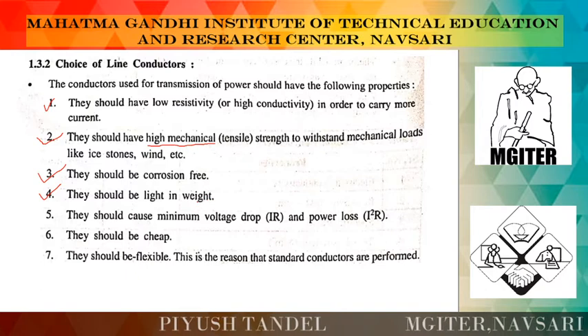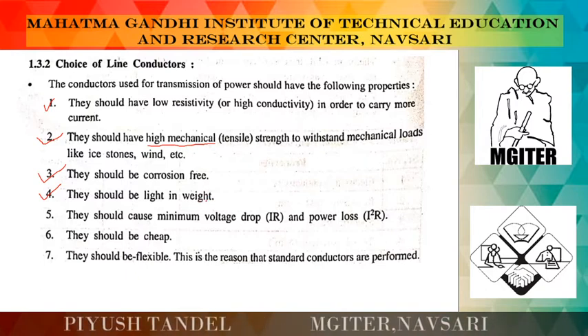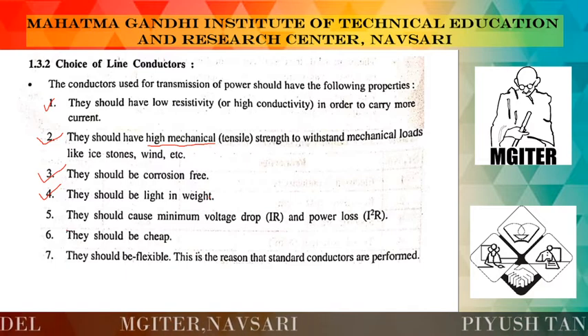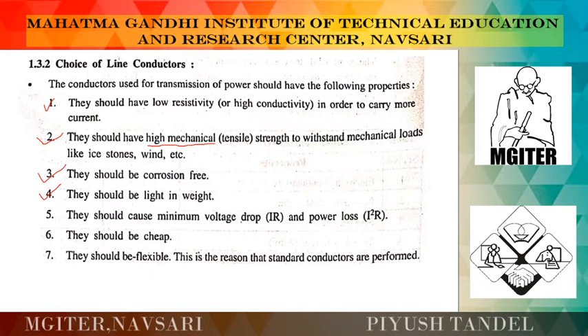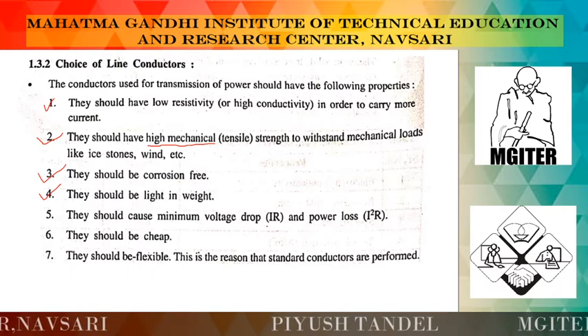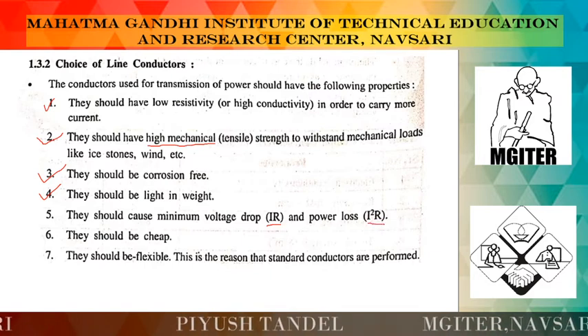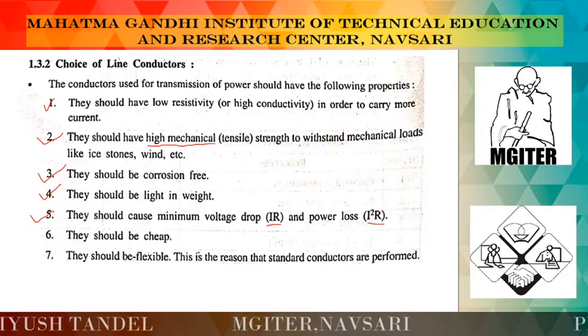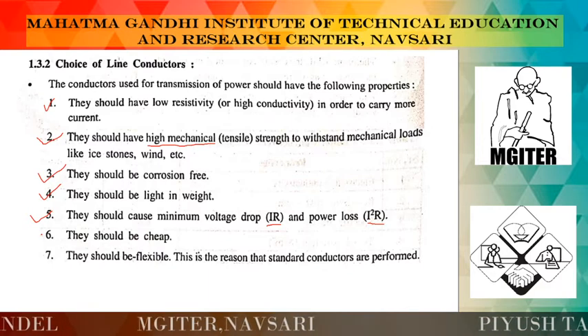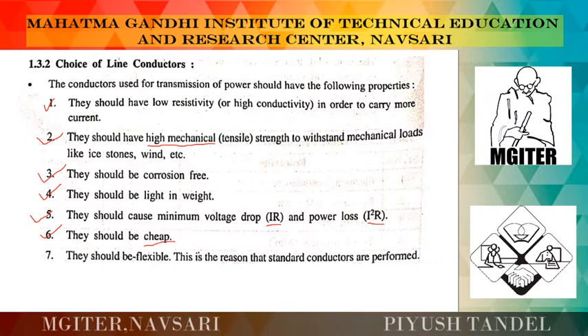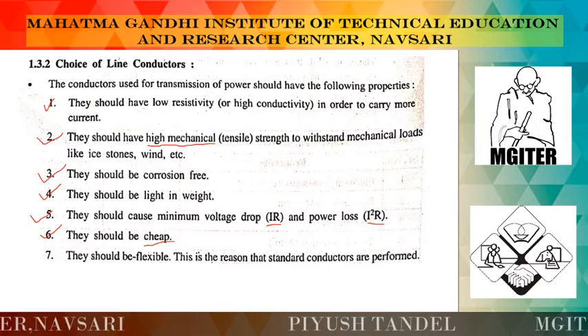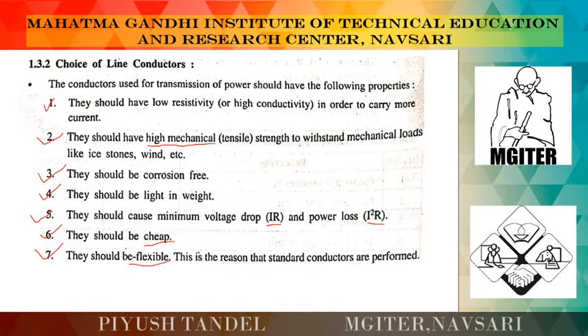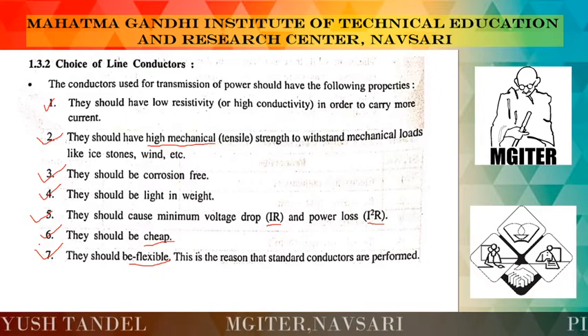Fourth, they should be light in weight, because if the weight of the conductor is light, the sag between the poles is also reduced and less mechanical strength is required. Fifth, they should cause minimum voltage drop — also called IR drop — and minimum power loss, that is I²R losses. Sixth, they should be cheap and economical to use. Seventh, they should be flexible, which is the reason that stranded conductors are preferred. These are the seven properties that a conductor needs.